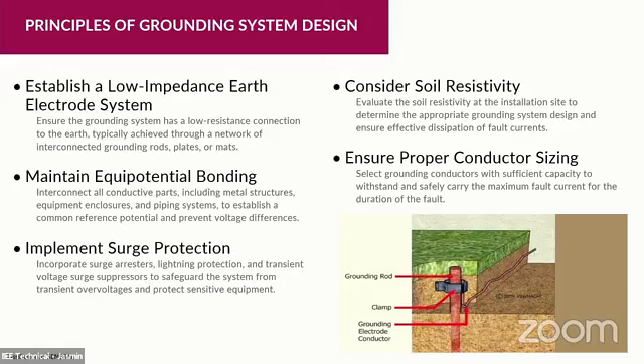We ensure that all metal parts in our system, such as structural steel, water piping, and of course equipment enclosures, which are metals, are bonded together and effectively connected to the ground. That way we maintain the reference potential and prevent voltage differences. If we maintain zero potential, zero voltage difference, technically we also maintain zero current whenever we have system faults. Yes. Next part of the principle is that we implement surge protection.